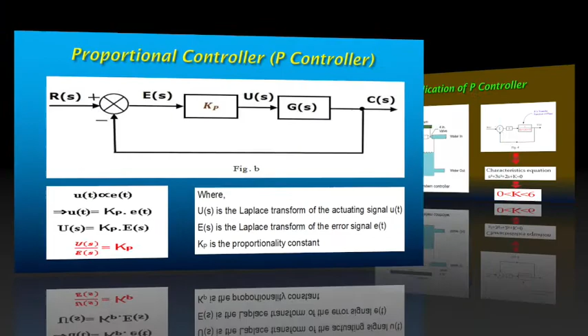Application of the P controller. Here, consider the liquid level system. In this system, the fluid level is directly connected to the control valve. When the level of the liquid rises, the valve closes in proportionate amount. This reduces the inflow to the vessel and vice versa. The inverse of proportional gain, or proportional sensitivity, is the proportional band and is defined as the change in the level necessary to operate the valve through full stroke. Basically, a proportional controller is an amplifier with adjustable gain.